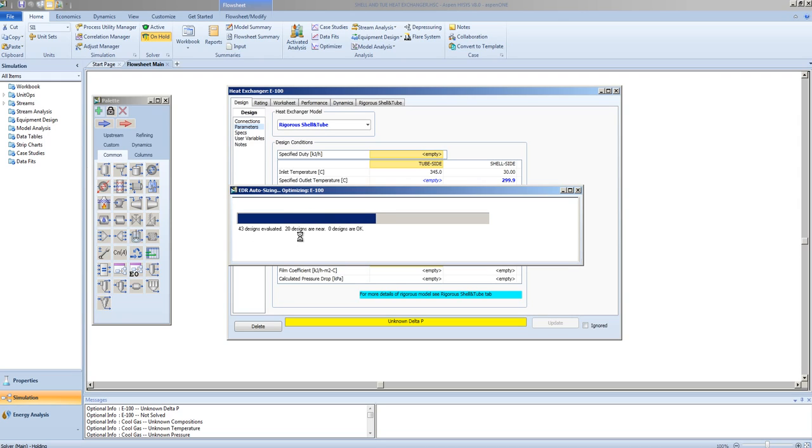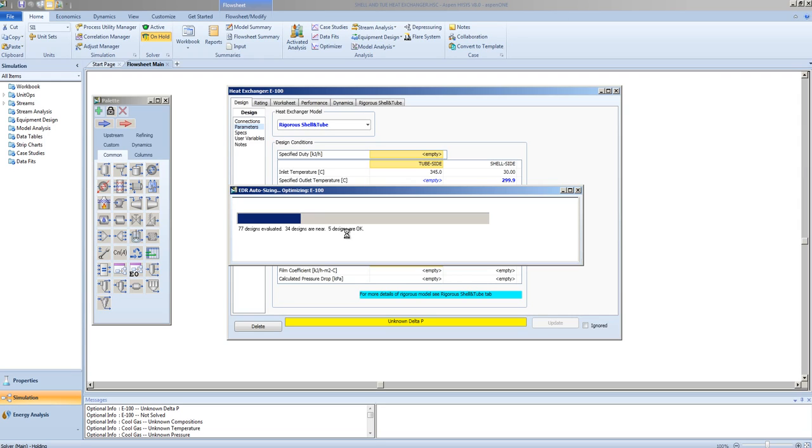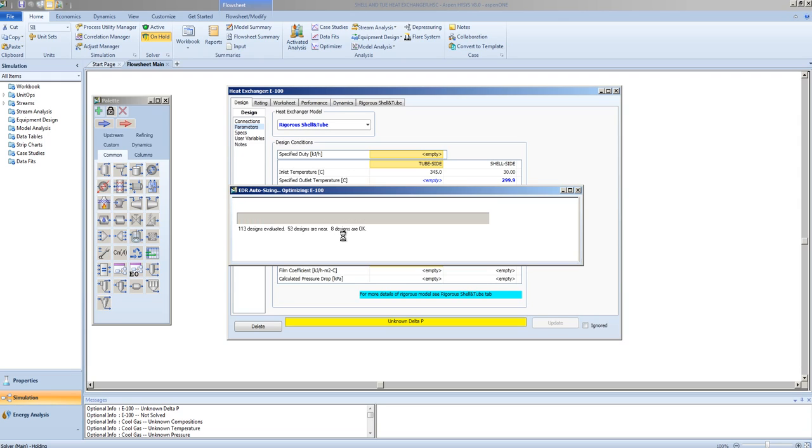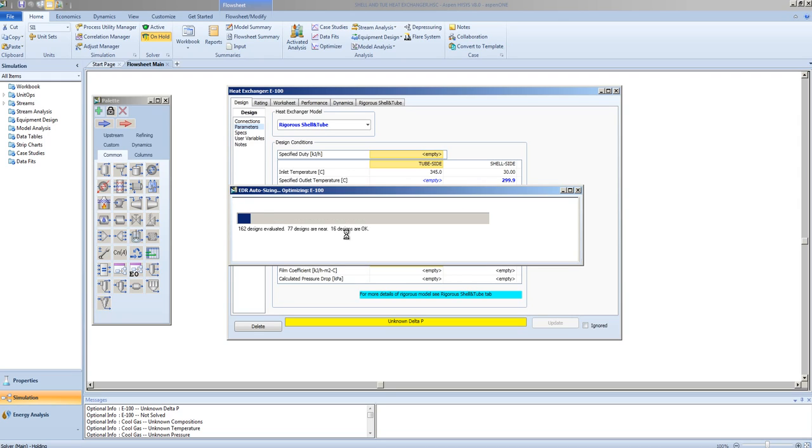Designs have been found that are near. Soon, we will find designs that are okay. Multiple designs that are okay will be evaluated to determine which is the most financially feasible design. These designs may have UA values that are higher than the UA value design. As such, the designs will be modified slightly by changing tube length or by changing tube diameter to determine which combination is best suited to the service.